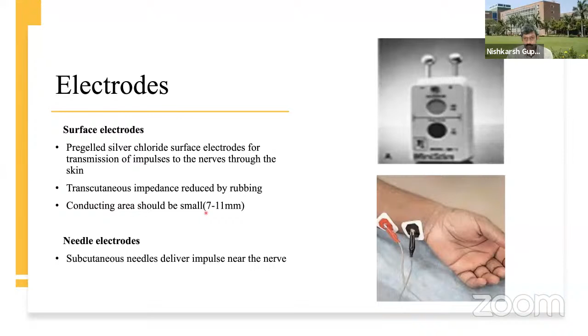Transcutaneous impedance can be reduced by rubbing the skin, and the conducting area of the electrode should be small, because if it is a very large conducting area, you may stimulate a lot of nerves in that area, which may give you a false reading. So it has to be small, about 7 to 11 millimeters.